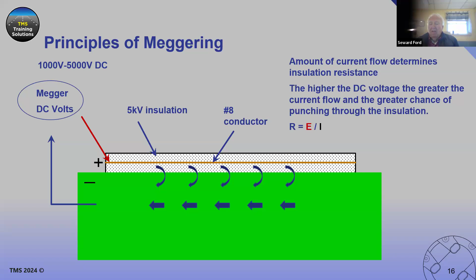How many megohms of resistance do we have? If I test today, it might be different tomorrow after heavy rain overnight — things change, which is why we keep accurate records and look for trends. There are trends and variations in the ground, but there shouldn't be rapid changes in the conductor's insulation itself; those changes are typically more gradual. That's what we're watching for, and that's okay.